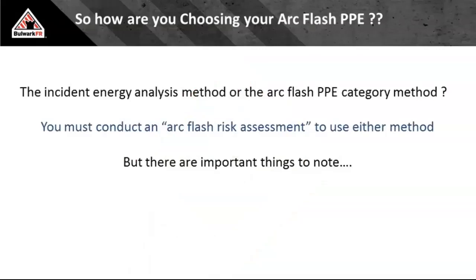So the question is, how are you choosing your arc flash PPE, or how are you communicating to your electrical team what arc flash PPE they need to be wearing? Well, there's really two methods. There's the incident energy analysis method, and there is the arc flash PPE category method, or more commonly known as the CAT method or the table method. You have to conduct an arc flash risk assessment to use either of them. There's some important notes to think about. There's pros and cons to each, but you have to do the calculations in order to know what the incident energy is to apply either of those.